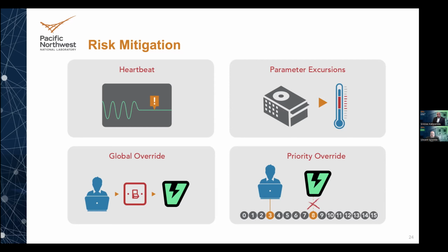We also have excursion limits. For example, shown on the top right, we have strict temperature limits, a low limit and a high limit, and we try to maintain temperature between those two. Once temperatures exceed or go beyond the low or high limit, the building automation system will release the space from participating in the event. That's another way to minimize the risk.